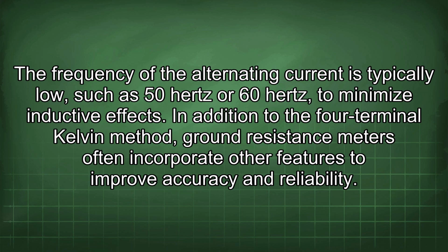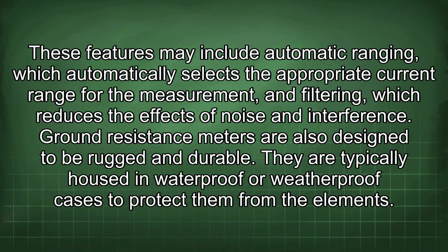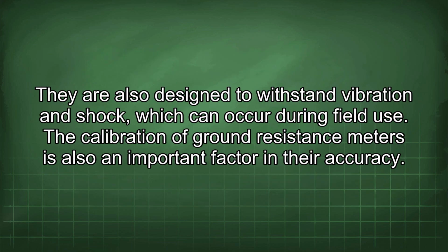In addition to the 4-terminal Kelvin method, ground resistance meters often incorporate other features to improve accuracy and reliability. These features may include automatic ranging, which automatically selects the appropriate current range for the measurement, and filtering, which reduces the effects of noise and interference. Ground resistance meters are also designed to be rugged and durable. They are typically housed in waterproof or weatherproof cases to protect them from the elements. They are also designed to withstand vibration and shock, which can occur during field use.